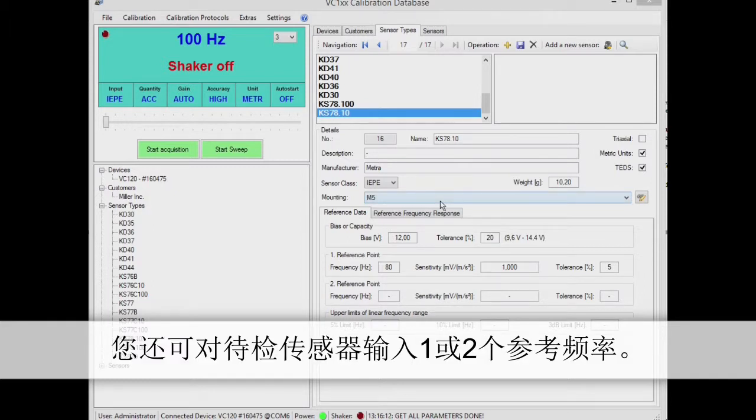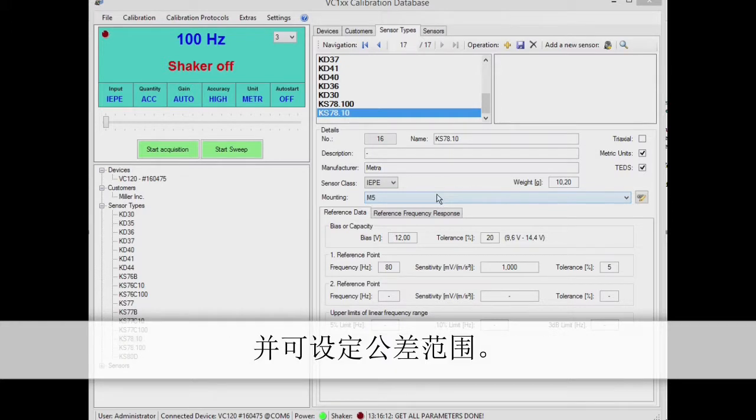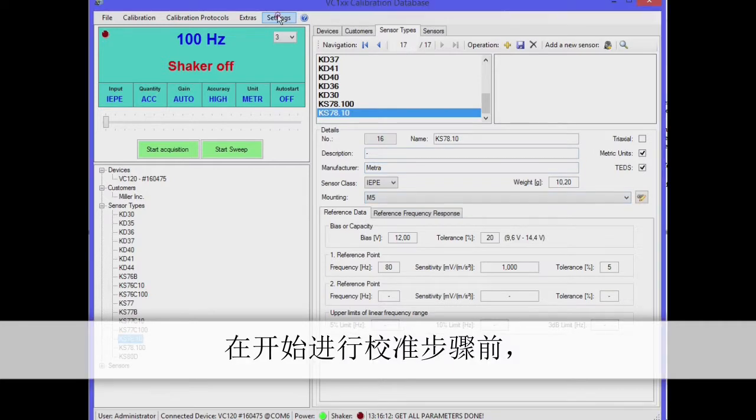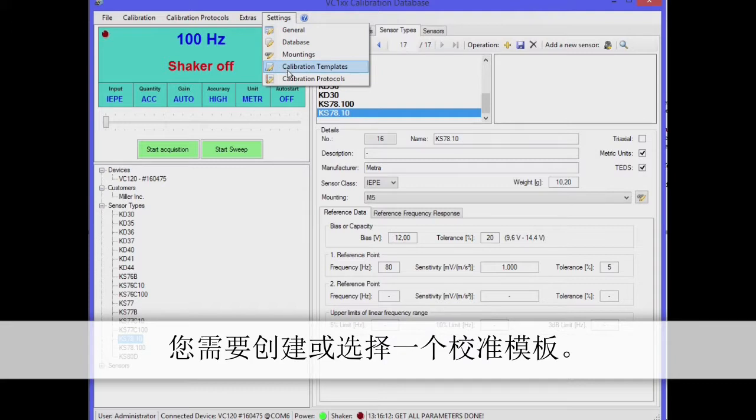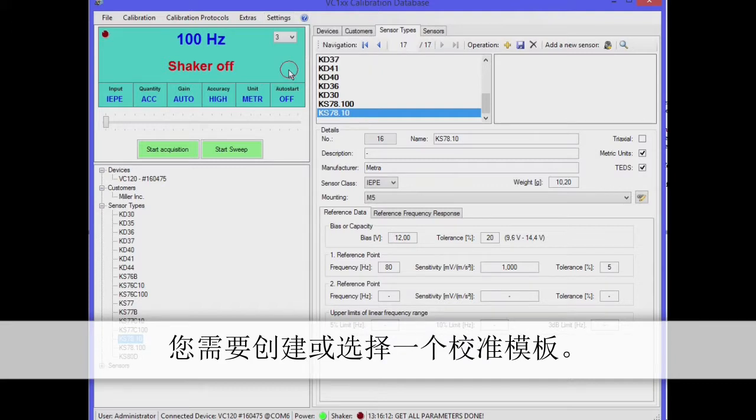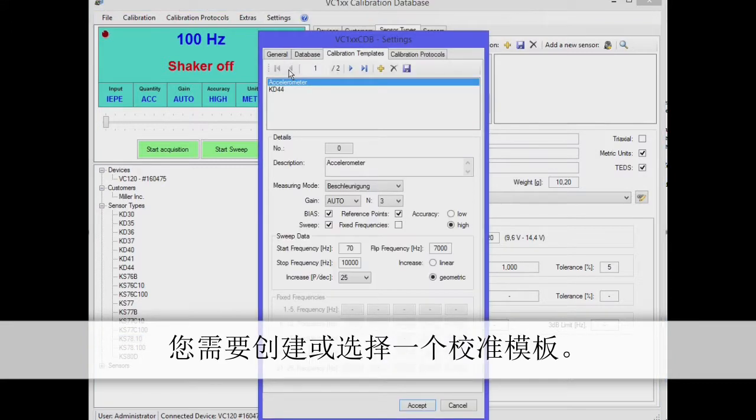You can also enter one or two reference frequencies to which the sensors should be calibrated. Entering the permissible tolerance will enable you to check the plausibility.